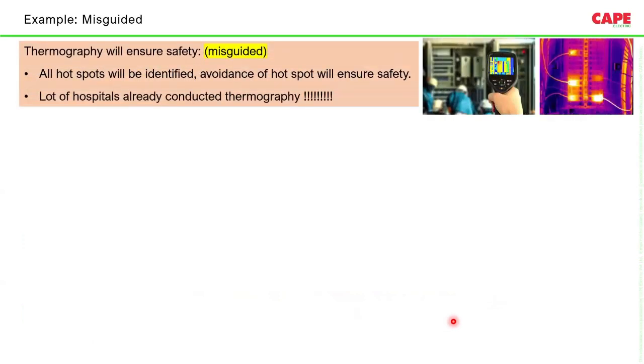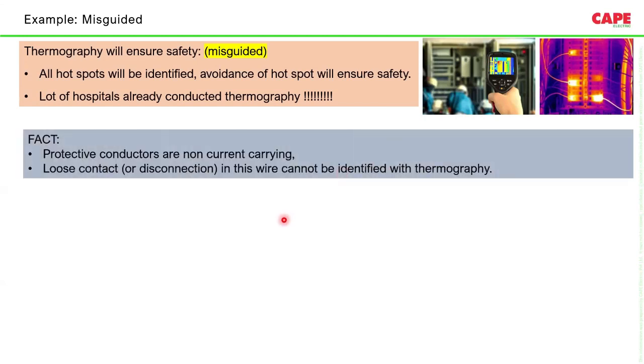One of the misguidings, I always make a comment about this. People think that by doing thermography, complete electrical safety is achieved or possible. Actually, this is wrong. Thermography can, of course, tell you the hotspots. It can increase the safety, but it doesn't mean that complete safety is achieved by doing only thermography. You have to carry out all the recommended safety measures as per IS 732. There are 18 inspection points and 10 testing points plus medical location additional testing. Over and above, you can do thermography. If you do only thermography, please don't think that we will achieve safety.